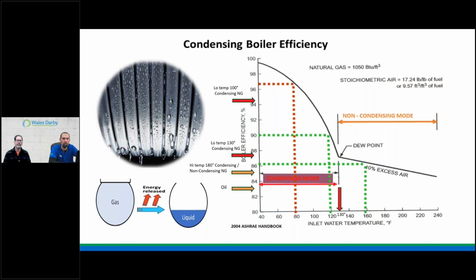Then if you go up and meet the dew point and go over, the first red arrow says low temperature 130 condensing, and we're sitting at, well, let's just call it 87%. Is it that? I don't know, it might be less. But if you go down to the next orange or gold arrow, it's like high temp 180, condensing / non-condensing, natural gas, fossil fuel. And that's where we sit, because if you follow that arrow where it hits the dew point line, you're sitting at that 160, 170, 180, right? So really, we're not achieving what maybe we believe the label is telling us we should get, and that's not the case at all. Now, where do we actually see those efficiencies of the high 90s, right?